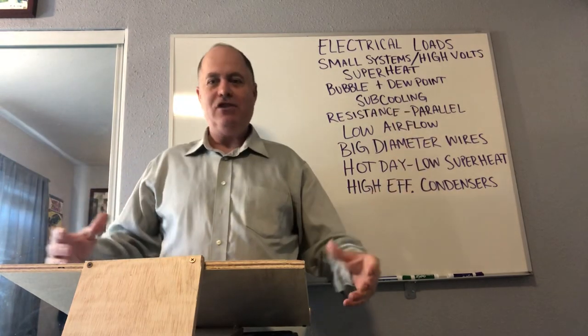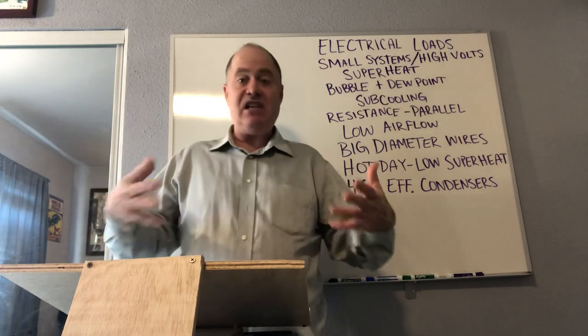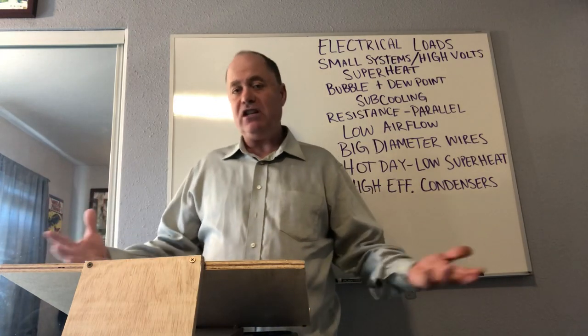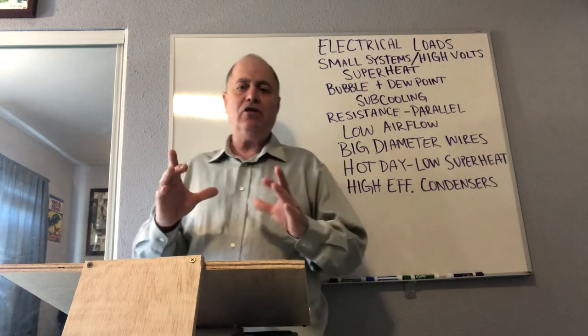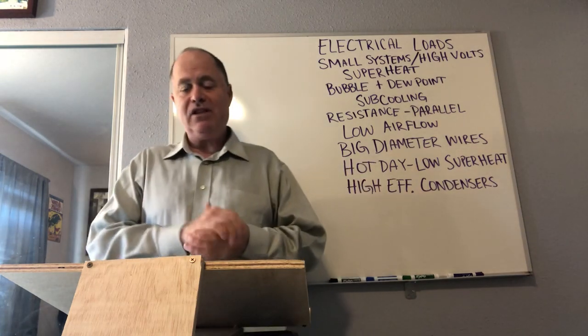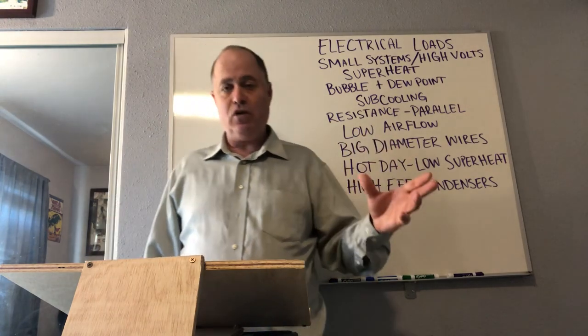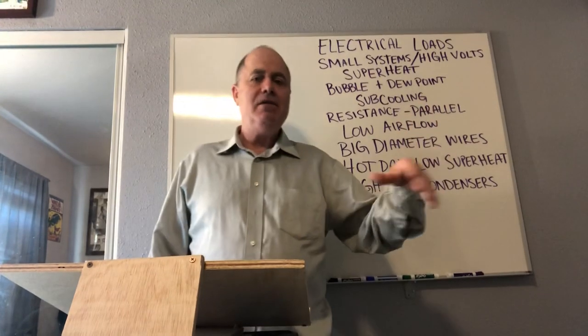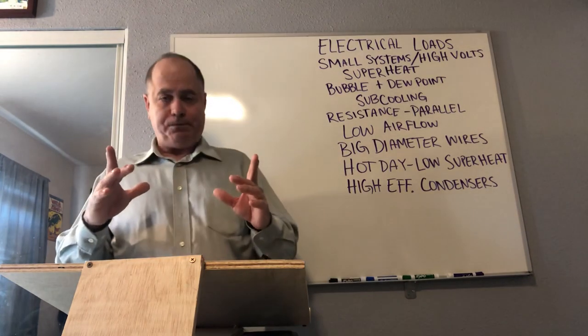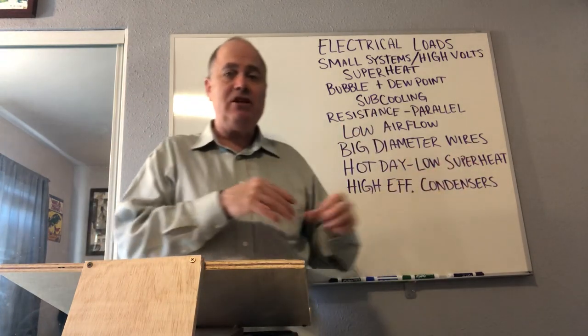Superheat sounds like a lot of heat. The origin is pretty direct — superheat was really about steam, superheated steam, locomotives, and different machines in the early to mid-1800s. But in air conditioning and refrigeration, in the refrigeration cycle, we're mainly concerned about superheat on the suction line. And the suction line is actually a cold line — it's cold to the touch when everything's working okay, which is the opposite of what you'd think. Superheat is the number of degrees above saturation, or above the boiling point of a substance. We're very concerned with superheat on the low side to make sure we have vapor with an insurance policy built in going into our refrigeration or air conditioning compressors.